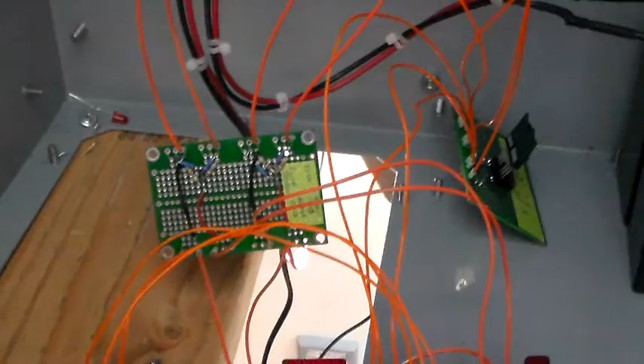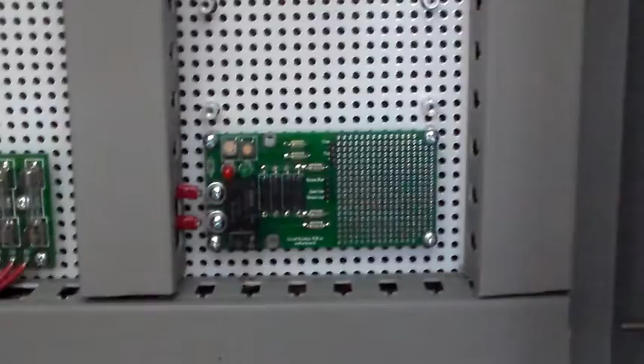But what we're doing in this case is we are measuring ambient temperature using a semiconductor sensor. We are also measuring station power voltage, which is the DC voltage used to trip and close our circuit breakers. We're also measuring the bus voltage off of the solar power. And the circuit breakers, there's one right there, there's one right there. This particular one, circuit breaker number 1, is the one that's going to be controlled by this data acquisition unit.